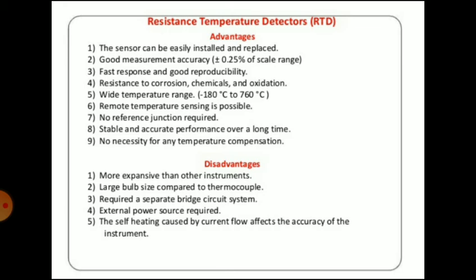Now we will see some disadvantages: more expensive than other instruments, large bulb size compared to a thermocouple, a separate bridge circuit system is required, an external power source is required, and the self-heating caused by current flow affects the accuracy of the instrument.